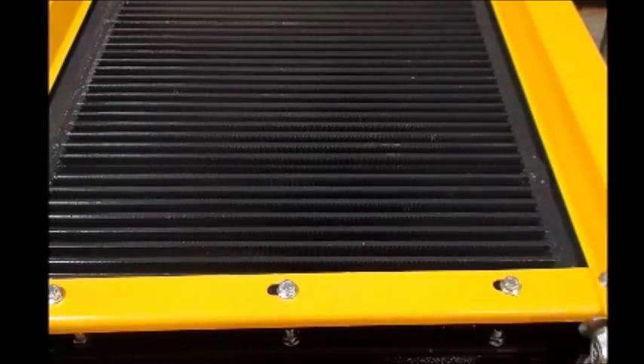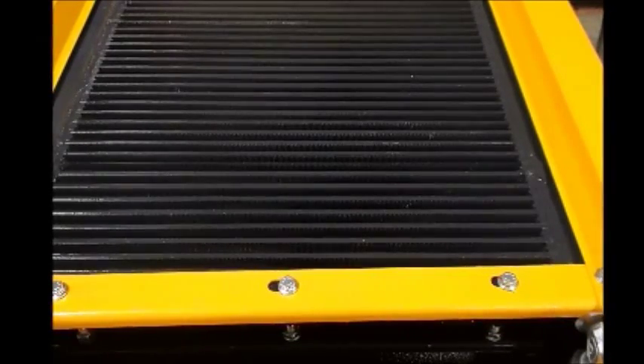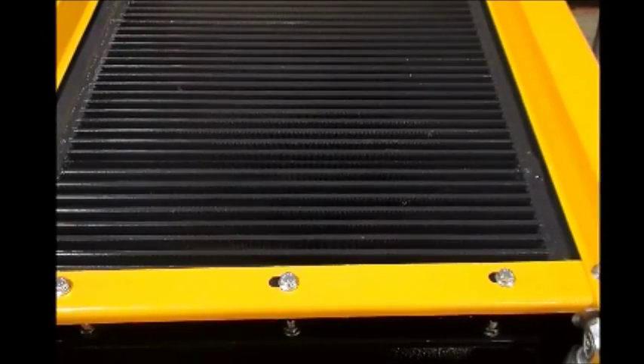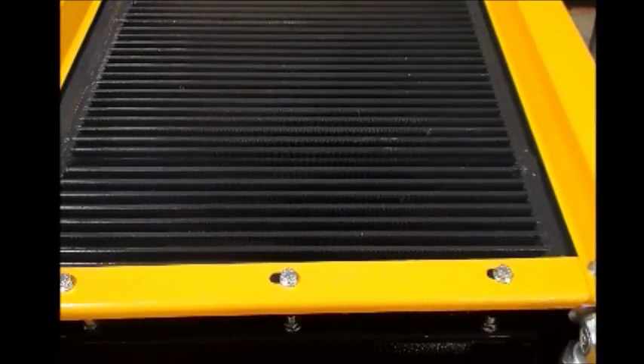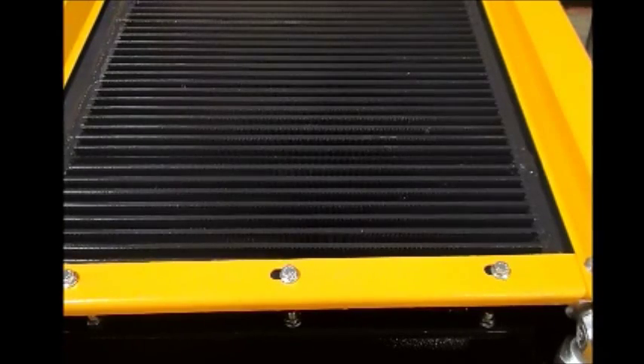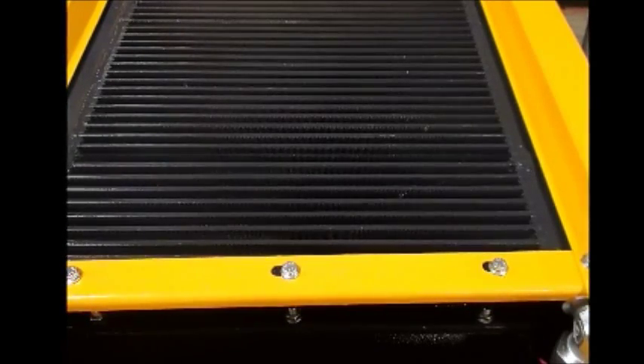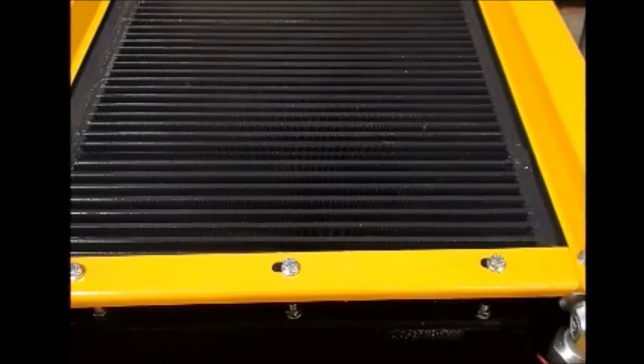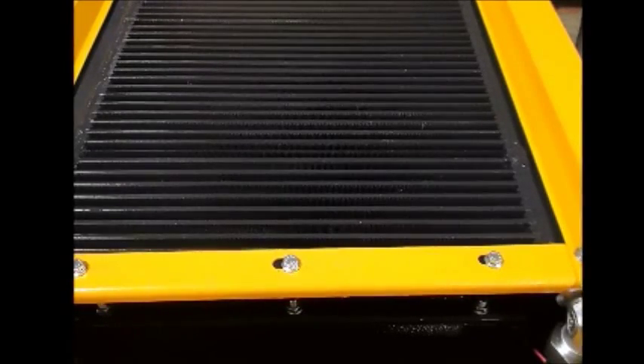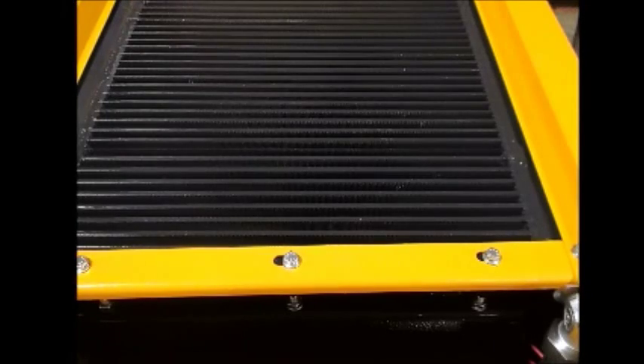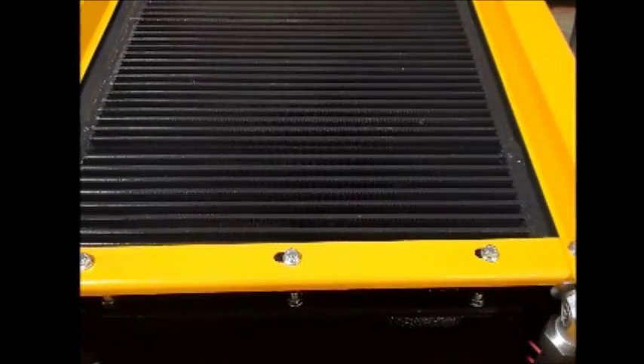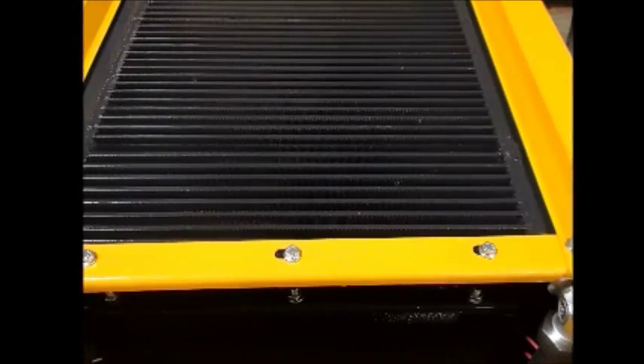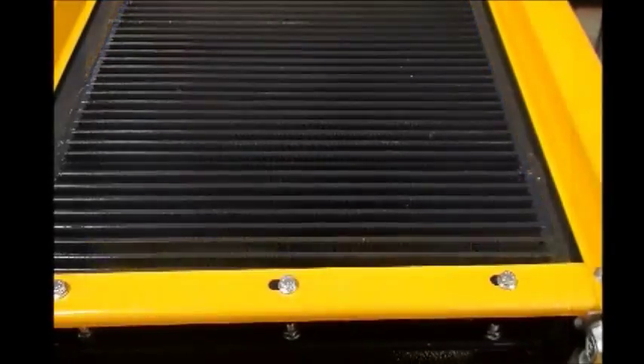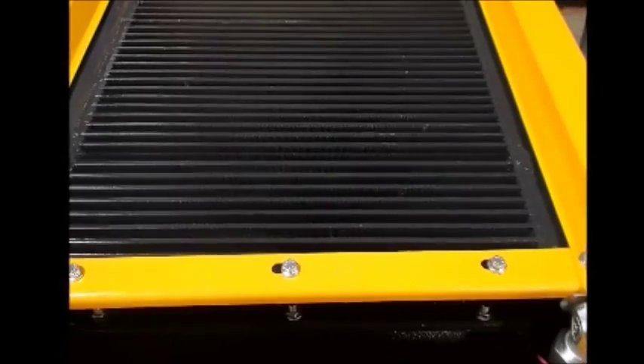The air-cooled aftercooler portion of the radiator lowers the temperature of the outlet compressor air to within 10 degrees approach from ambient air temperature. A cooler outlet air temperature also reduces humidity levels in your air storage system and makes for a more efficient dryer if used. The aluminum radiator design has large inner cores, reducing pressure drop, permitting maximum airflow, which is another energy-saving feature of our compressor. So hot air? I can assure you it won't be coming from us.